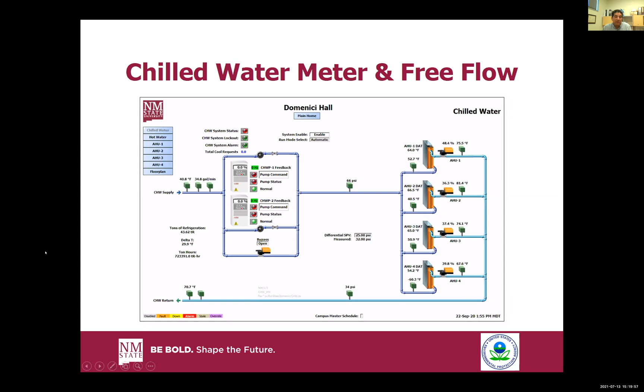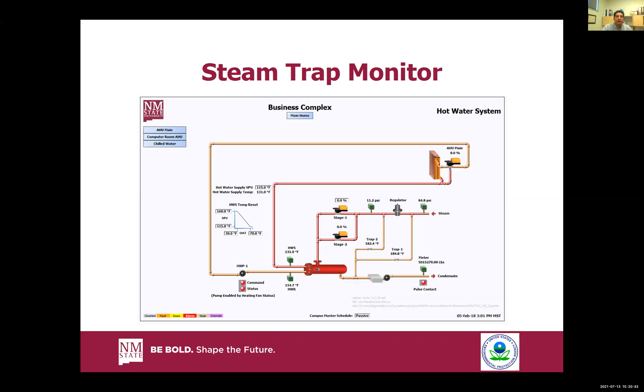But steam can become very inefficient if it does not reach its destination. And so we actually have monitors on certain lines that will tell us if the steam is actually bypassing its intended use. If it's not making it to the building, we can monitor and determine when we're having a malfunction of that system, just with the implementation of a few strategic sensors, because that's a huge energy loss if we're not really sure where our thermal units are going.